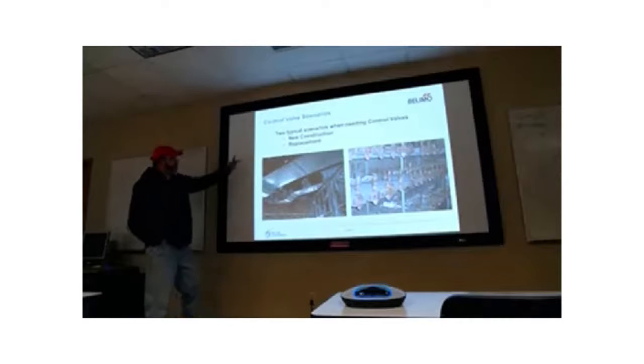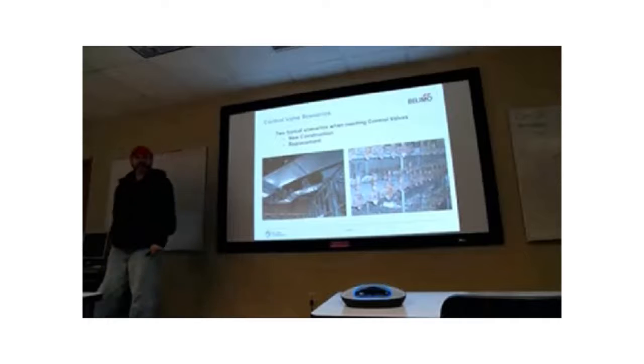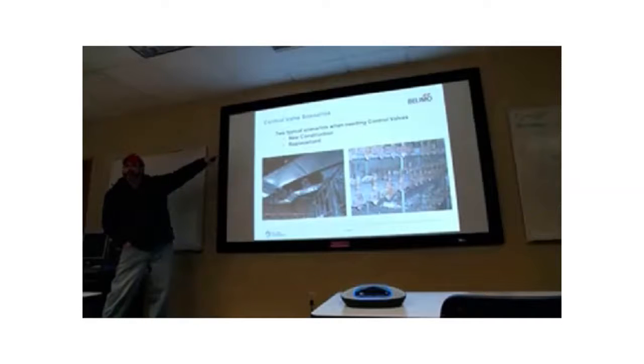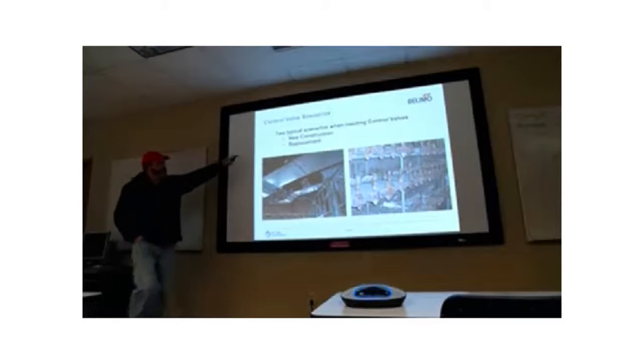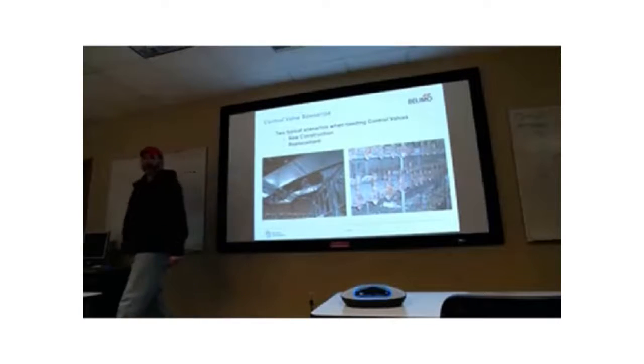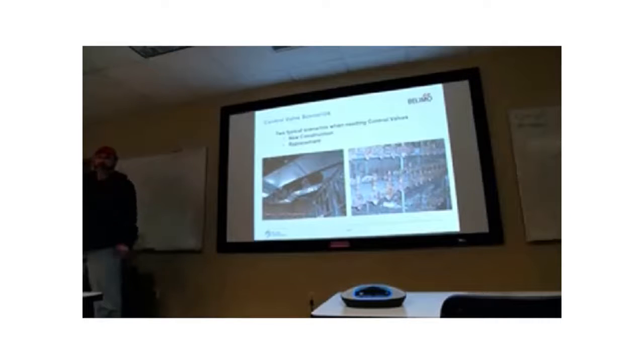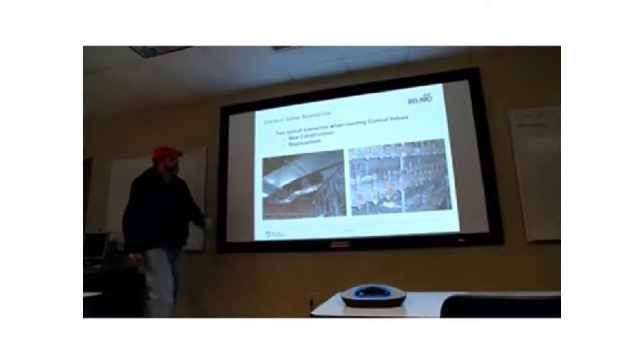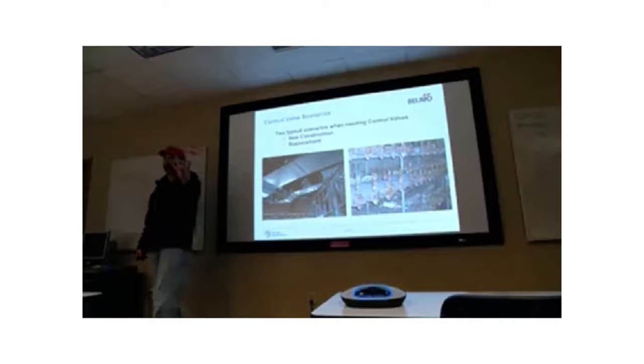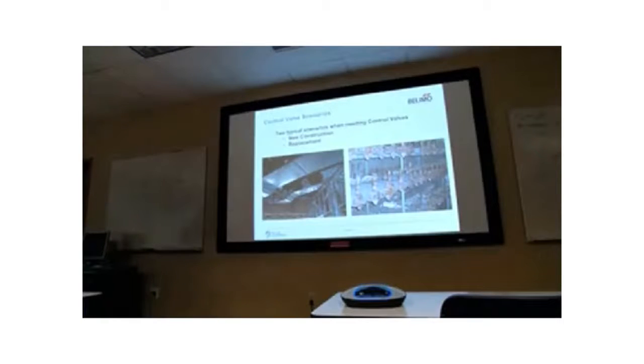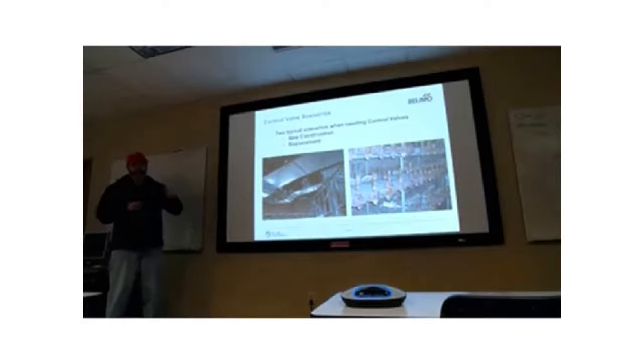So this is pretty common sense, right? New construction or replacement. Now there's another term that we use. There's new construction, which is new stuff. There's replacement. What's that other word that starts with R? Retrofit. So what does retrofit mean, you think? What it means, and this is how I'm going to define it, is if you say replacement to me, I mean you want to replace that whole control valve assembly, which means the body and the actuator. That's replacement. Retrofit would be either replacing the valve body, not so common, or more commonly the actuator. That's what I mean when I say retrofit, in terms of valves.